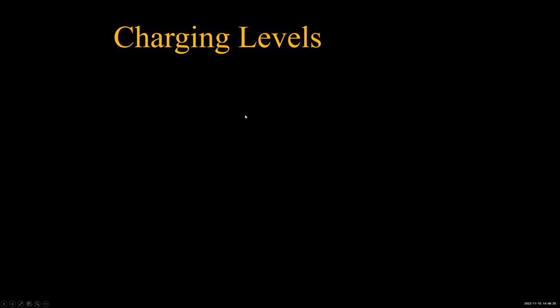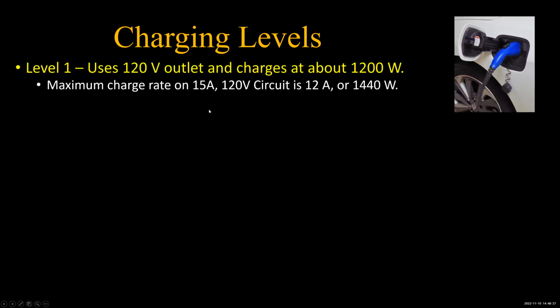Now let's talk about charging levels. Level 1 uses a 120 volt outlet, charging somewhere up to 1,440 watts. The reason is so they can be used on a 15 amp circuit—12 amps is the maximum continuous current allowed on a 15 amp circuit. If you're charging for more than 3 hours, you might pop a circuit breaker.